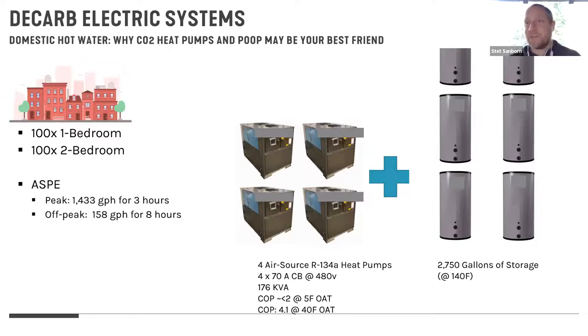That connected load is probably the most restrictive piece of the domestic hot water design component for our multifamily buildings. So it's something that we have to keep an eagle eye on. So this is air source heat pump plus storage. And remember, the air in the wintertime is not a great source to pull energy from for heating hot water. So this is probably my most expensive option on the table, and it's going to cost the most to run.